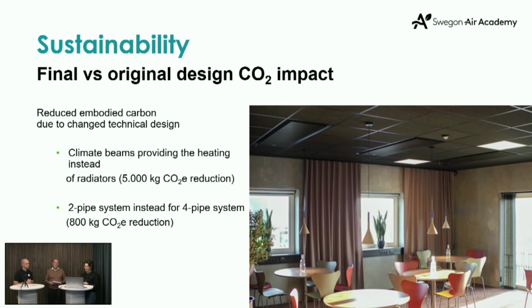In this specific case, since we have removed the radiators and are heating with climate beams, we have taken away 5,000 kilograms of carbon dioxide equivalent emissions. That's a lot. Also, by going from a 4-pipe system to a 2-pipe changeover system, we are reducing an additional 800 kilograms of CO2 emissions. All in all, I think we have around 3 kilograms per square meter of reduced CO2 on the embodied carbon only.